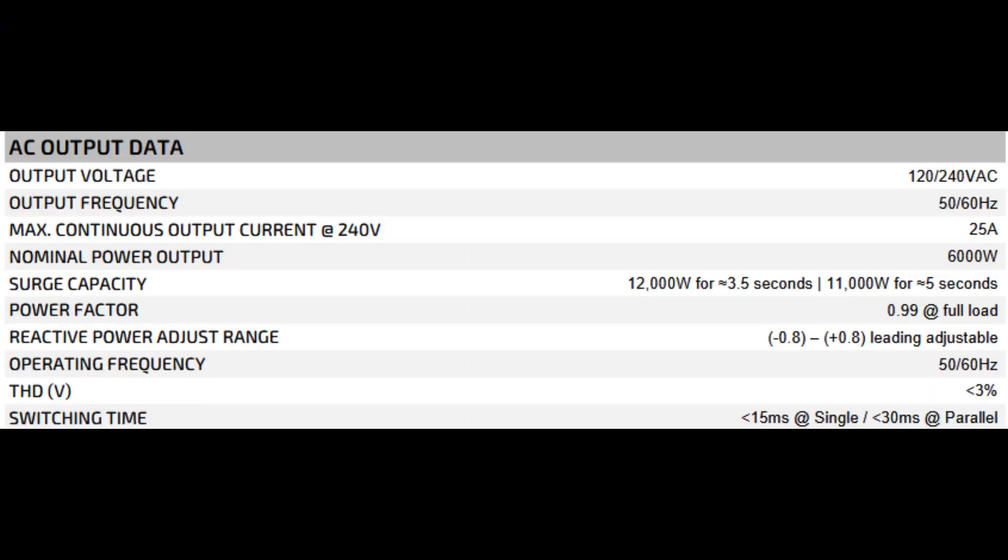Next we've got AC output data. Output voltage 120-240 volts AC. Output frequency 50-60 hertz. Max continuous output current at 240 volts, 25 amps. Nominal power out 6 kilowatts. Surge capacity 12,000 watts for approximately 3.5 seconds or 11,000 watts for approximately 5 seconds. Power factor 0.99 at full load. Reactive power adjust range minus 0.8 to plus 0.8. Operating frequency 50-60 hertz. THD 3%. Switching time 15 milliseconds at single, 30 milliseconds at parallel.